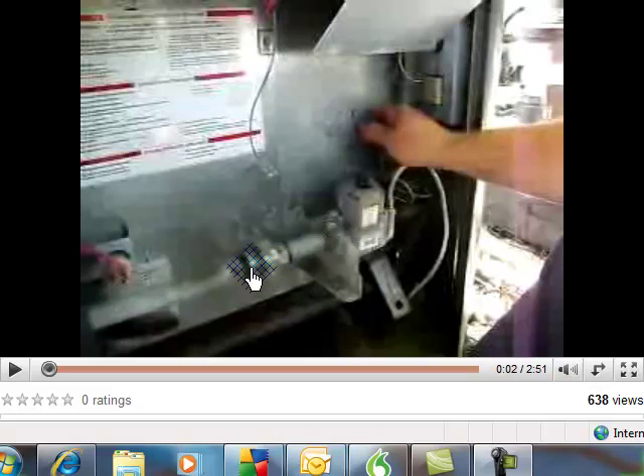You put the pipe in. He said any kind of lubricant, any kind of sealant, which again is wrong for gas. You have to use gas-approved Teflon tape or whatever. Usually Teflon tape is yellow. It has to be approved for gas because it can cause certain chemical reactions and things you don't want. But this is wrong. We're going to watch the video.